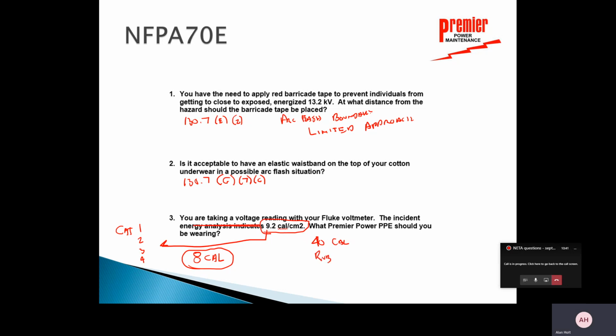We're going to have our rubber gloves. Remember, rubber gloves with leather outers for everything over 50 volts. So we've got the rubber gloves on, our safety glasses on, hearing protection, and leather footwear. So that should cover us. Now, understand that if it was under the 8 calories, all this would stay the same, except we wouldn't have the 40 cal suit on. We have our hard hat and our face shield and our balaclava there. A lot of times people forget about the balaclava portion of it.